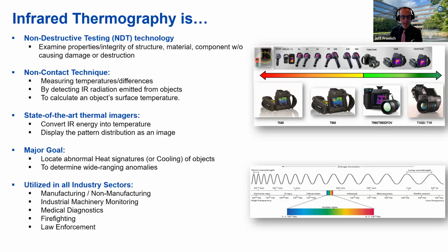And so it's important. You might have a visual arc flash plastic Lexan shield that, when you open up the control cabinet, will be present for arc flash protection, part of the manufacturer's optional adds. And while you can see through it, the infrared technology cannot scan through it. I always like to use the expression, it's like kryptonite to Superman. So you have to have a line of sight.